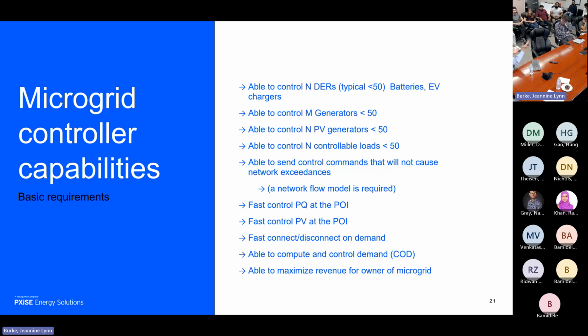Now, some microgrids only have one battery, but some have multiple batteries, and some have multiple DERs, some have multiple generators. So the software needs to be written in a way so it can have an arbitrary number of these. Now, our software is currently set up to these parameters. I think we'll probably keep it that way. Now, this brings up another issue of what kind of controller can you buy from an RTU vendor that will control this number of devices at 60 hertz? There are none.